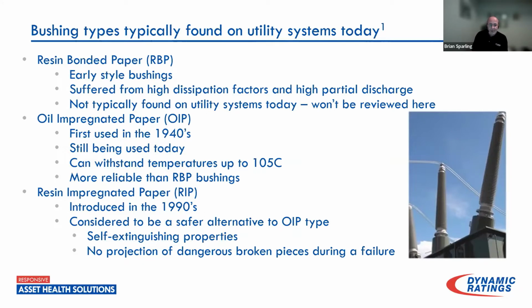In the 1990s, we began to see the introduction of what we call resin impregnated paper, or dry type high voltage bushings. These were considered to be a safer alternative to OIP by virtue that there is no oil inside the RIP type bushing. It's a dry insulation system. So if and when these things fail, you can reduce the risk. There is no risk of explosion and shrapnel going from the porcelain on the high voltage bushings when they have failed catastrophically. So more and more now people are moving in this direction.